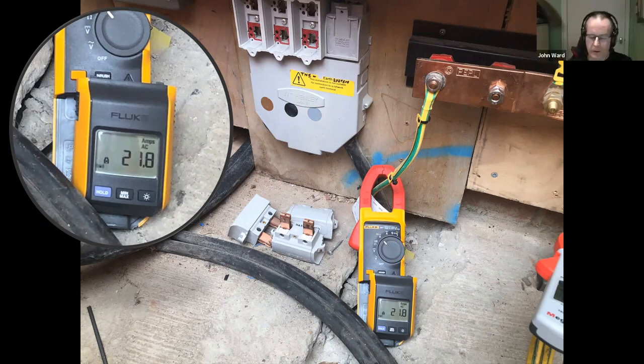It's all fitted into how, if you're going to have your power coming in, that might be one earthing system. But if you've got island mode, where you might run your house from a set of batteries in the garage, that might have its own separate earthing system, a TT installation. To achieve that, you can't be connected to the incoming TNCS service, so there's provision to actually switch the protective conductor or main earthing conductor coming in.